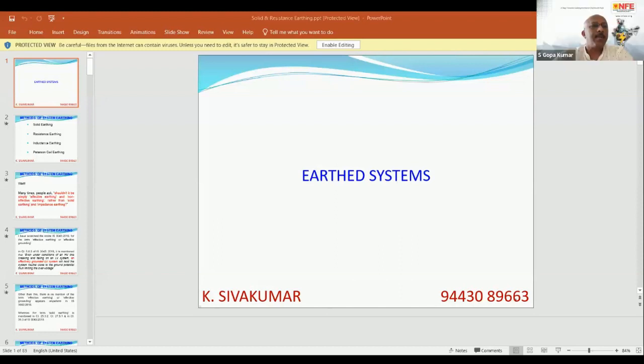Okay, so there is a question. In a single phase to earth fault, not only zero sequence current, but negative and positive sequence current also are possible due to capacitive currents. Is it right?